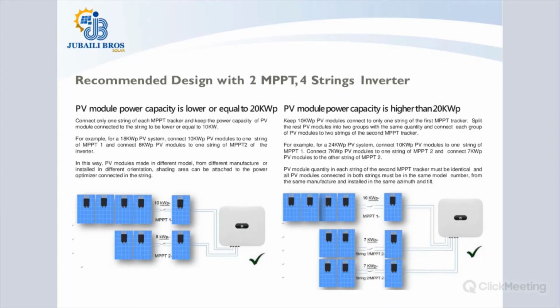And again, we will take a look at one final recommended case. For the same 20 kilowatt inverter, we are going to do an example in case you are sizing a system that is slightly higher or slightly lower than the total DC wattage. So for example, this is a 20 kilowatt inverter. In this first case, we are sizing an 18 kilowatt system, which is slightly lower than the 20 kilowatts. Let's all remember that the maximum DC power for each MPPT is what? It is 10 kilowatts, isn't it? So you can connect 10 kilowatts to MPPT1 and the remaining 8 kilowatts to MPPT2. Very, very acceptable. So you are doing 18 kilowatts, maximum 10 to the first MPPT, and the balance to the second MPPT.